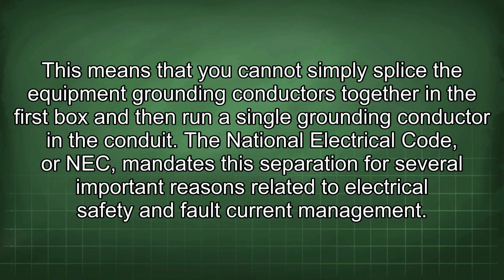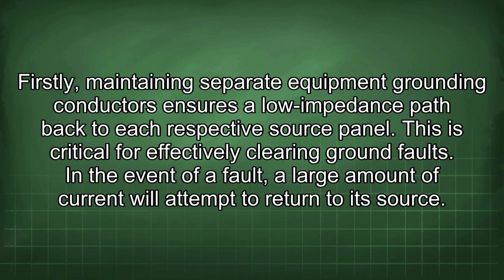The National Electrical Code, or NEC, mandates this separation for several important reasons related to electrical safety and fault current management. Firstly, maintaining separate equipment grounding conductors ensures a low impedance path back to each respective source panel. This is critical for effectively clearing ground faults.